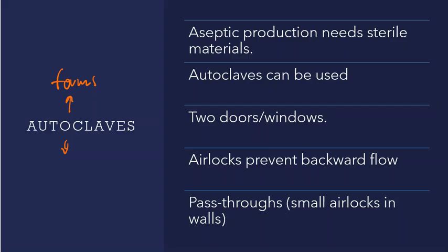So I want you to go back and think about previous modules that we've talked about so far. The idea is to get them to 121 degrees. The idea is to get them to a certain pressure, for instance 16 psi, and to hold them there for so many number of minutes. Let's just say that is what the SOP tells me to do.